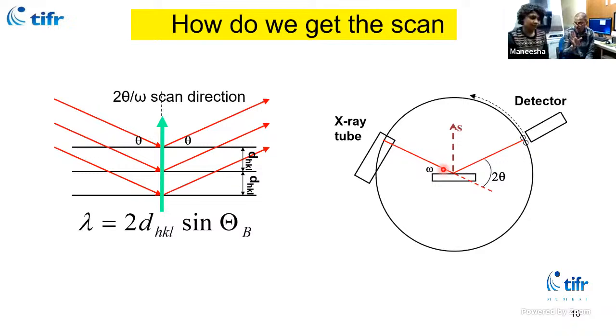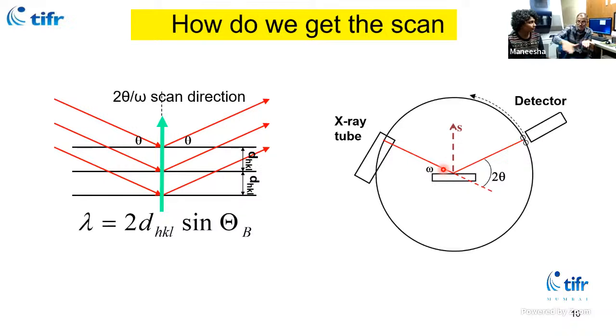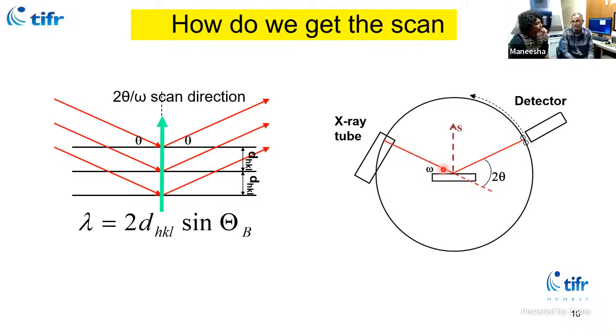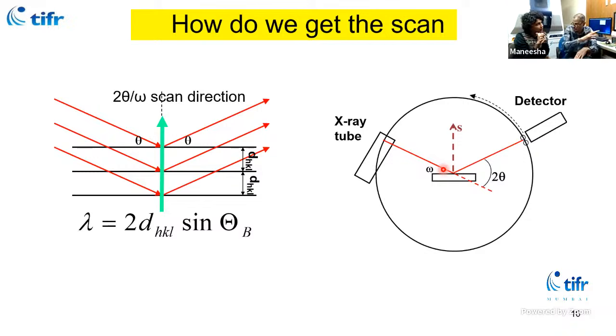We will see if we get any peaks from NaCl. A question arises: does the thickness of powder on the plate affect the result? The sample holder is specially made so powder is just up to the surface — not more, something like 100 to 200 microns. It must match the center of the diffraction geometry. If using a different holder, you have to do height alignment, because if the height is wrong your 2-theta condition will not be satisfied at the correct angle.